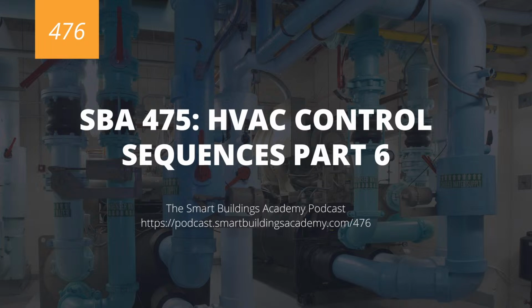These calculations will then be fed to your building automation system, which, based on set points, will make determinations of bringing on the lag chiller to back up the lead chiller, or bringing on a pony chiller, et cetera, just based on your sequencing.